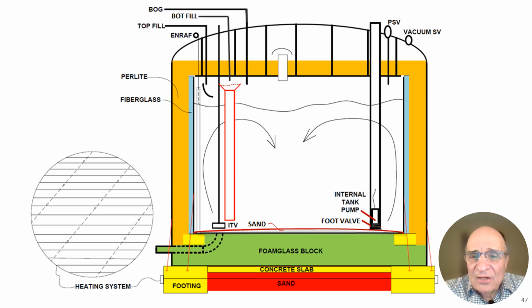And in this tank, you have LNG, and the LNG is continuously circulating around the tank. These are convective currents. Now, no one really knows the velocities of the currents. I've heard it said to be in the order of magnitude of 1 foot per second, but I won't say that as a fact, just as hearsay. But there is continuous circulation, and if there isn't, then you have stratification, which we've already spoken about.